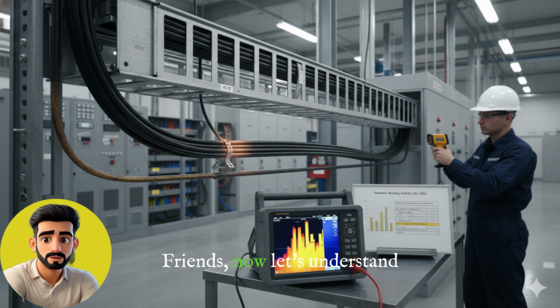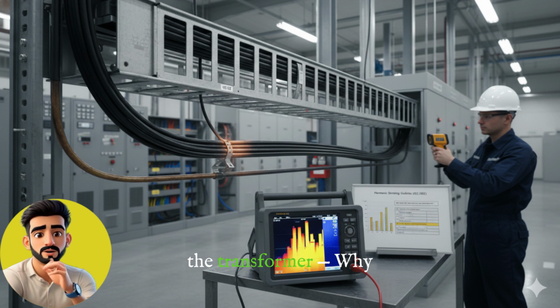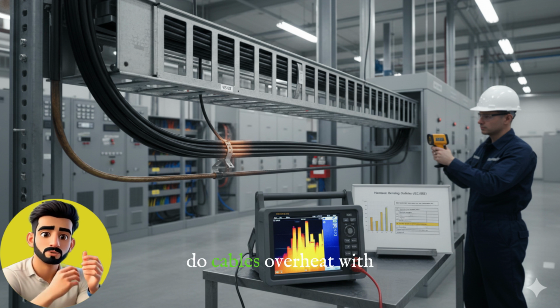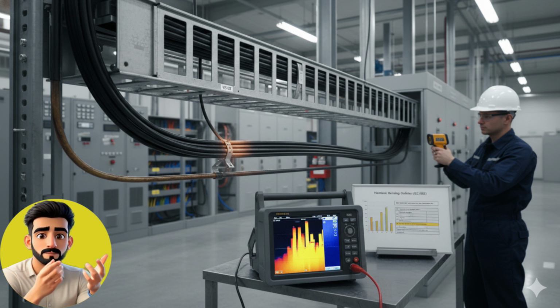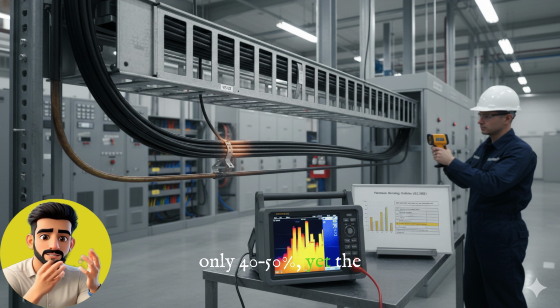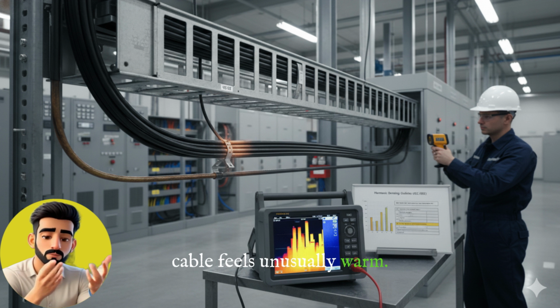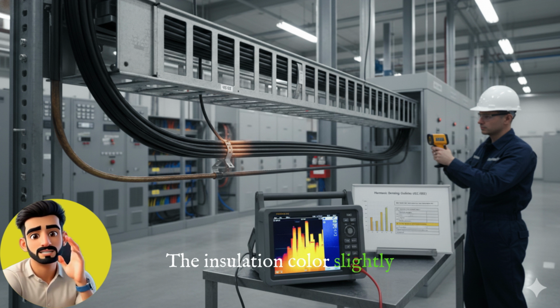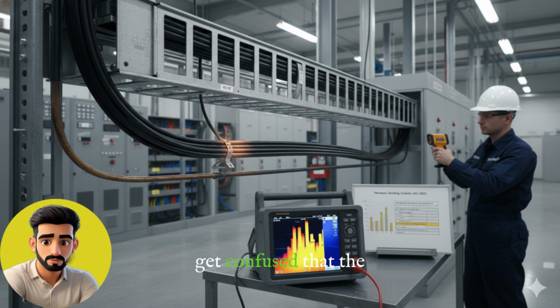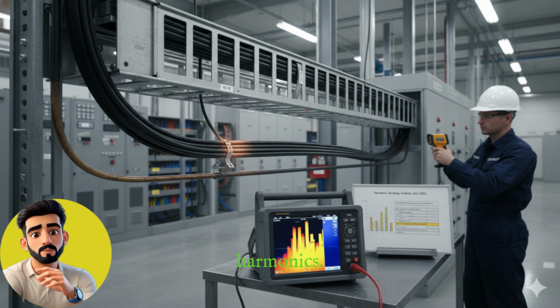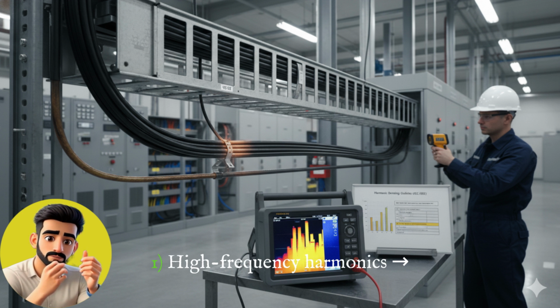Friends, now let's understand another critical point after the transformer. Why do cables overheat with harmonics? Many times it happens that the load is only 40 to 50%, yet the cable feels unusually warm. The insulation color slightly turns brown, and people get confused that the load is normal. Where is the heat coming from? The answer again: harmonics. 1.